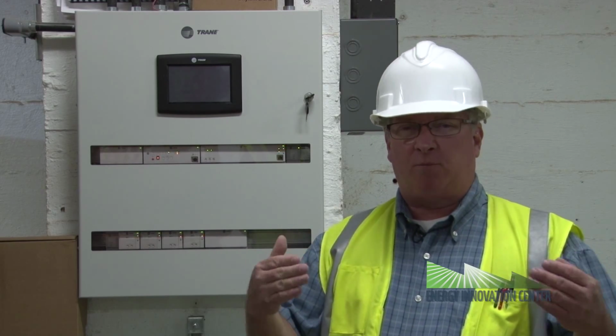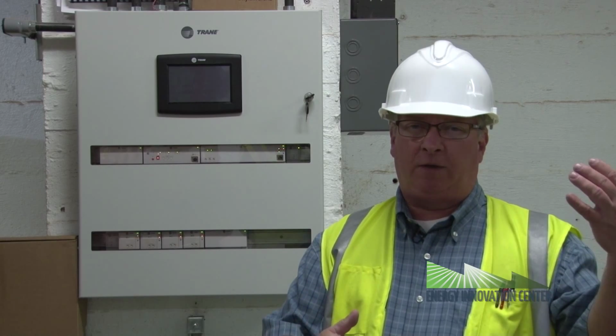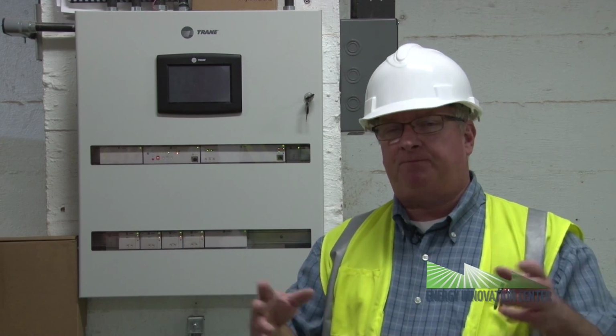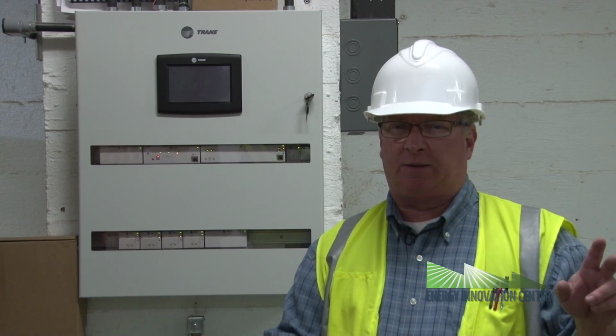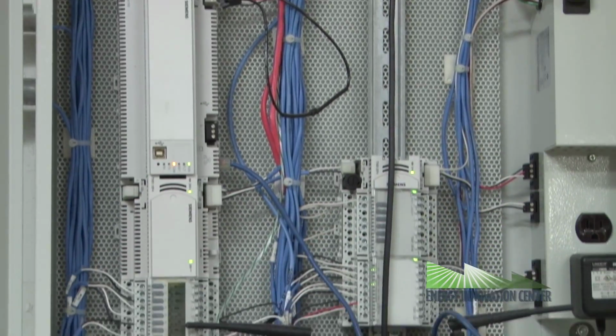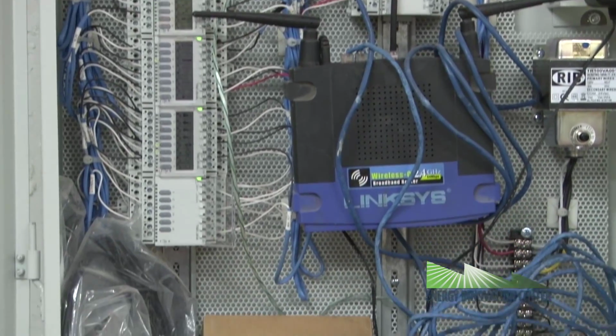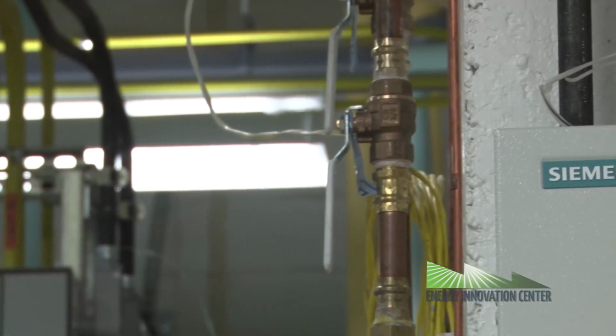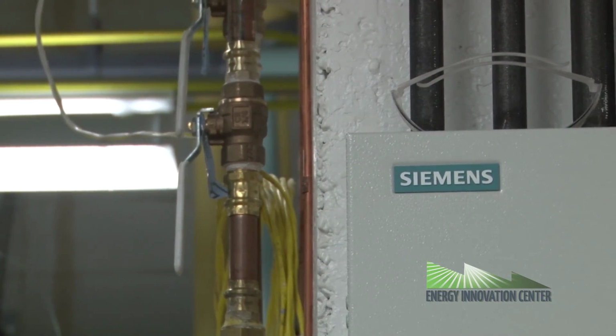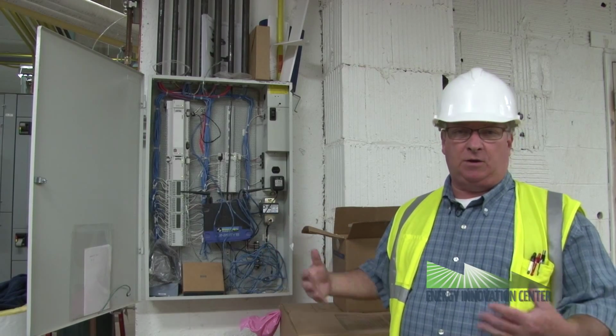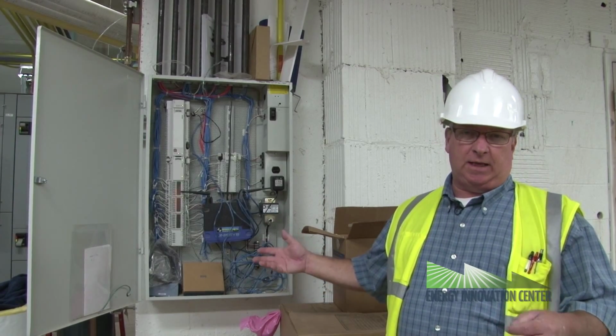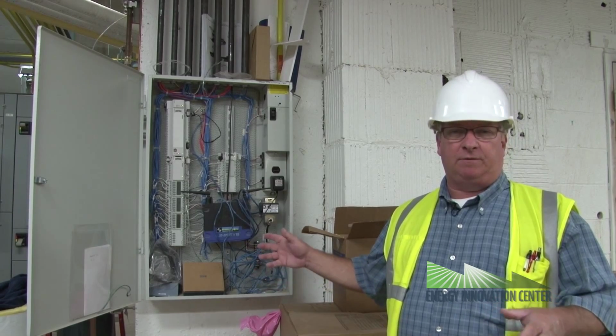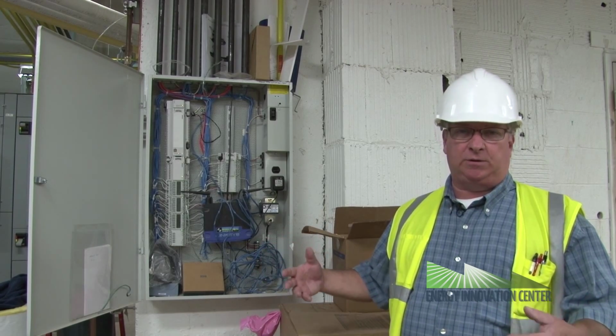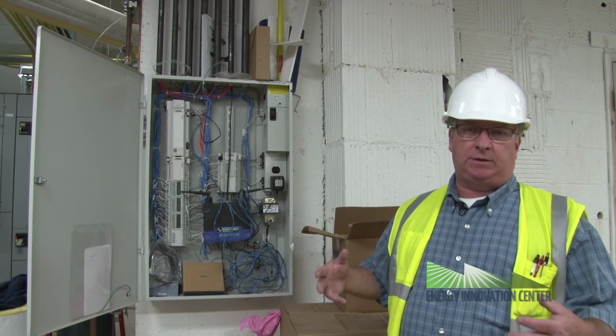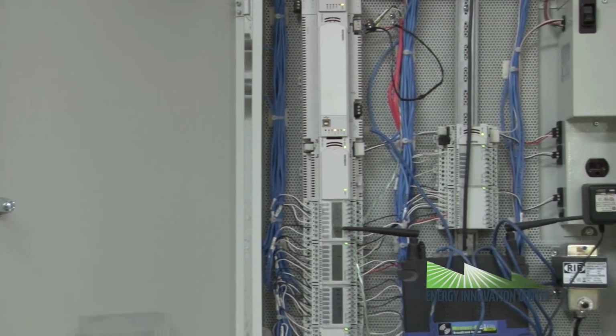Most buildings, if they have more than one automation system, have a front end for each system. We integrated that data here, and we're able to view it all off of one system, which is a bonus for the operators and the owners. Part of the base building automation system is a Siemens system. They're still working on this, adding all the points to it. At the end of the day, the building automation system will have over 5,000 points that we'll be monitoring throughout the building. It's probably 3 times what the normal building will have.